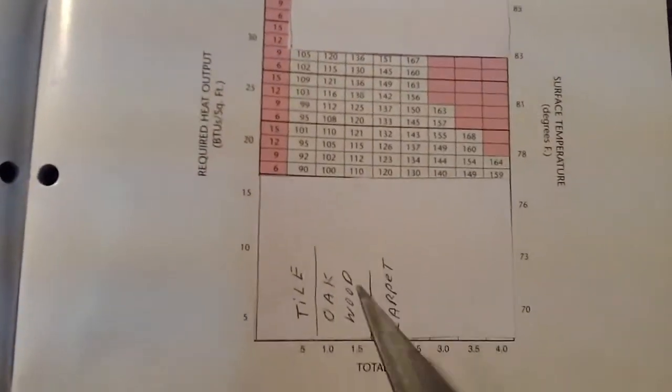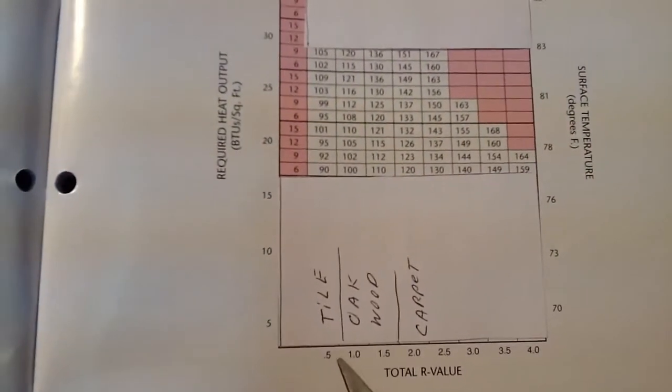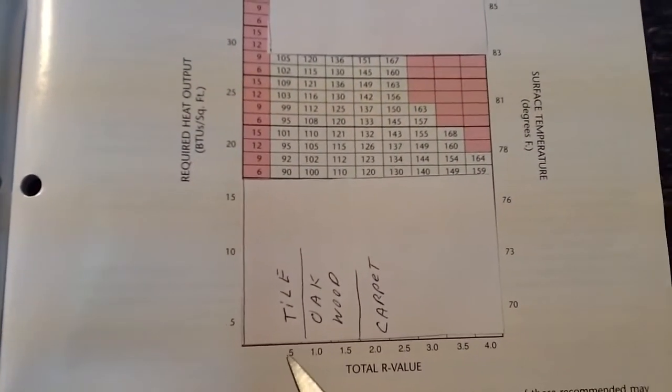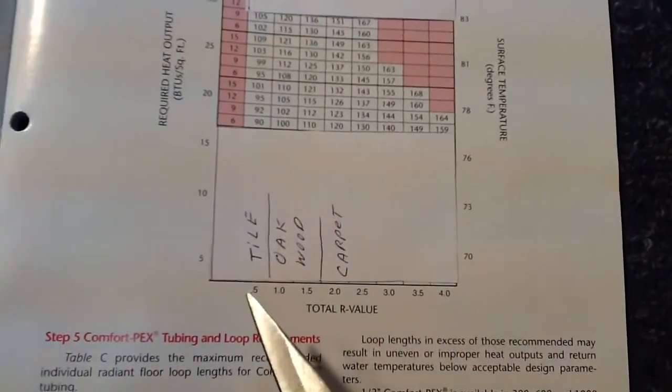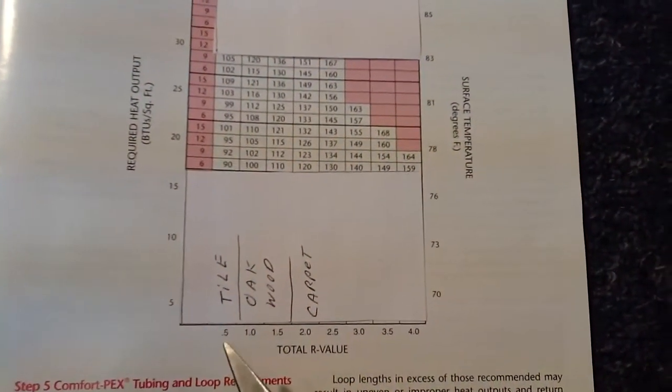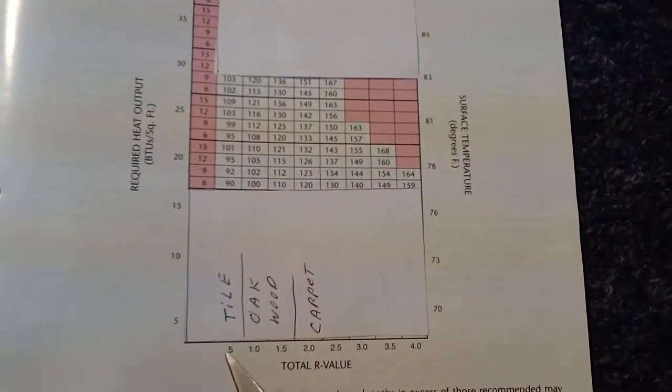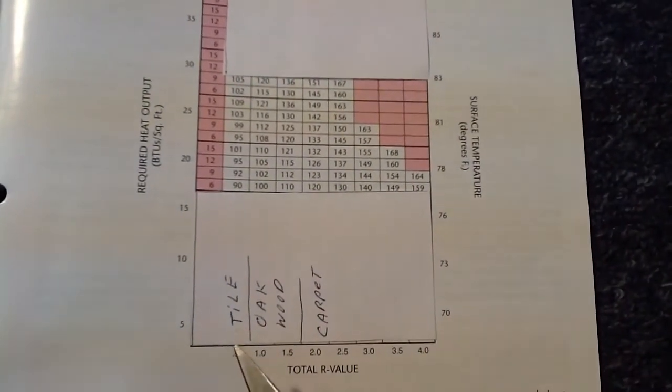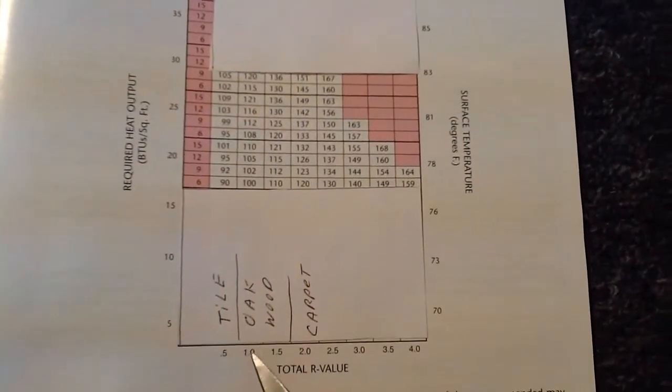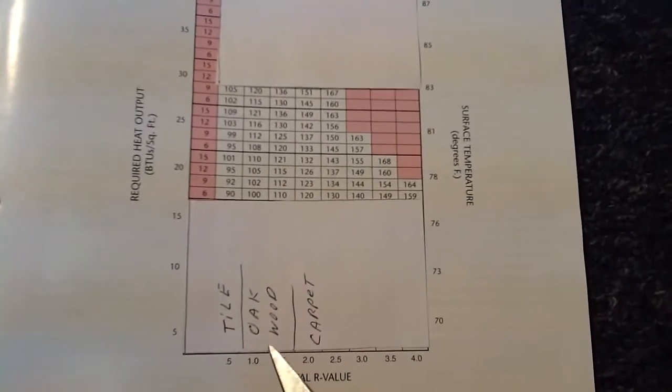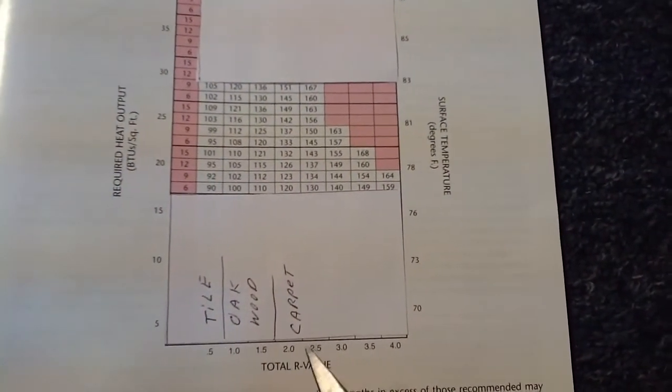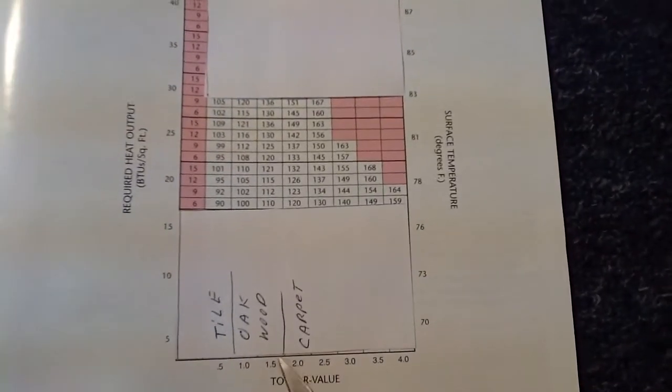As you can see, 0.5, which is probably mud tile, that's R, the resistance, the R value, 0.5, very little, the radiant gets through it very easy, probably tile. 1.0 to 1.5 is wood, normally oak wood floors. Once you get to two and larger, that's carpet and carpet with padding.